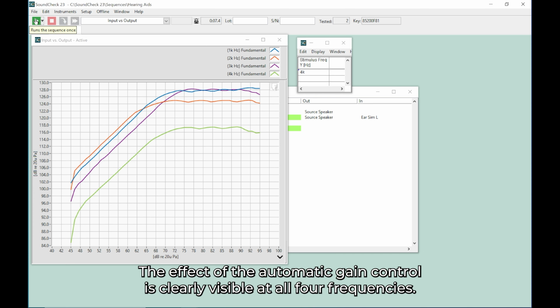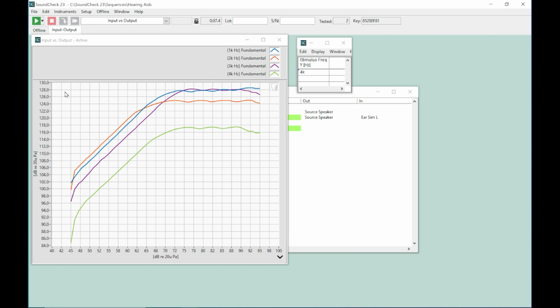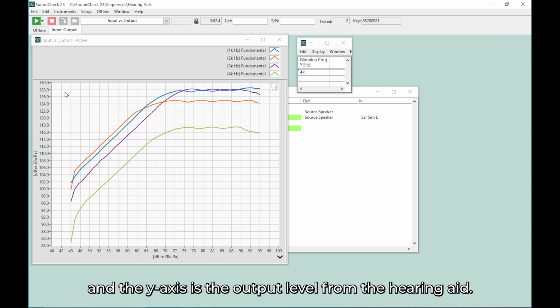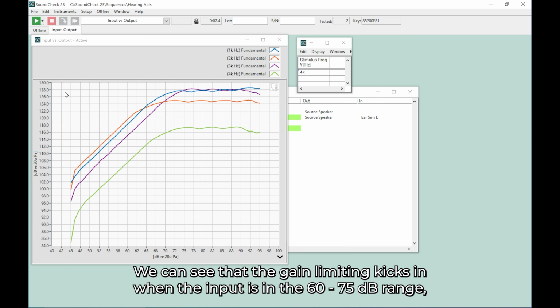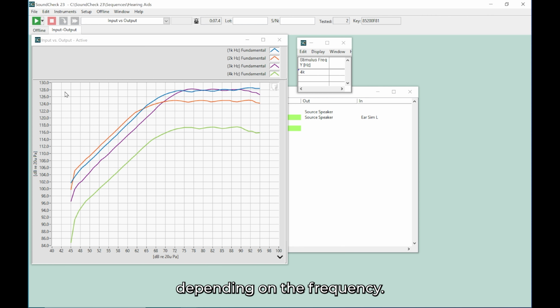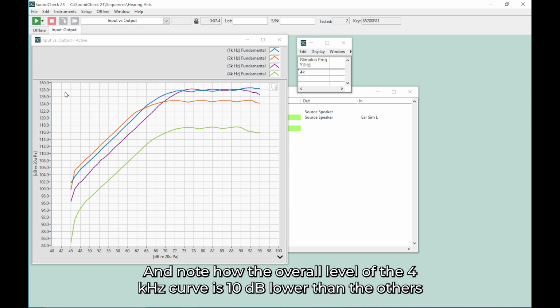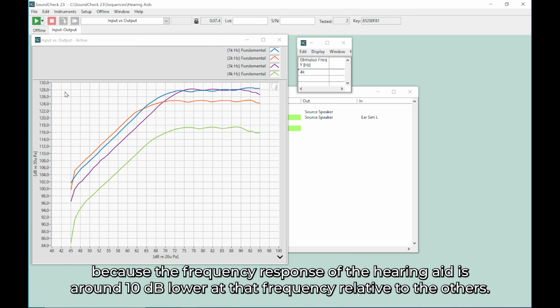The effect of the automatic gain control is clearly visible at all 4 frequencies. The x-axis represents the stimulus level, and the y-axis is the output level from the hearing aid. We can see that the gain limiting kicks in when the input is in the 60 to 75 dB range, depending on the frequency, and note how the overall level of the 4 kHz curve is 10 dB lower than the others because the frequency response of the hearing aid is around 10 dB lower at that frequency relative to the others.